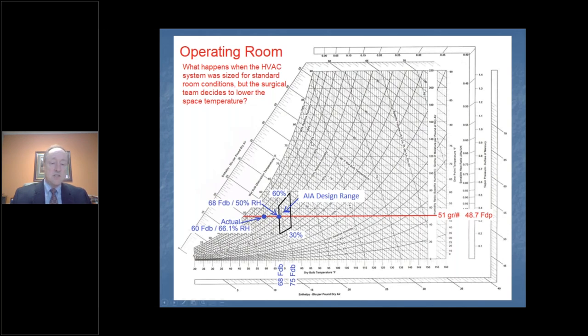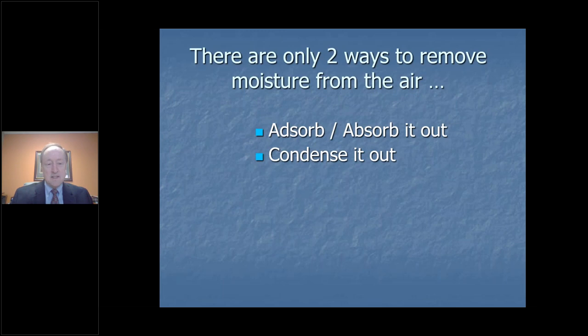You see 60 here, 70 here. So in that case, it's 60. And if you drop the temperature even lower, I see some operating rooms actually going down to 55 degrees, and you'll see you're at about 80% relative humidity there. That's a problem. So in the next few minutes, and we'll wind up with these, there are two ways and only two ways to get moisture out of the airstream. You absorb it out or adsorb it, depending on the type of desiccant that you use, liquid or solid, or you condense the moisture out.